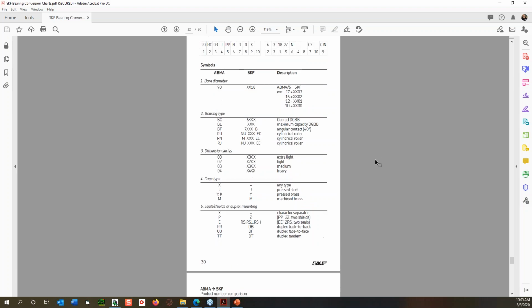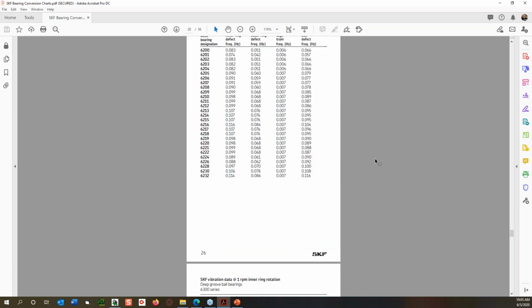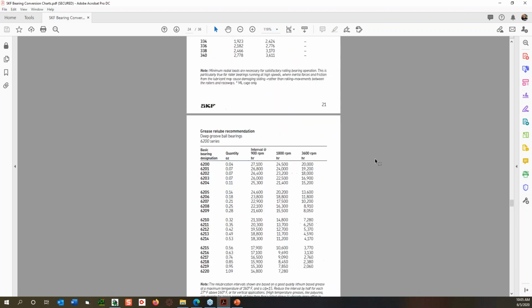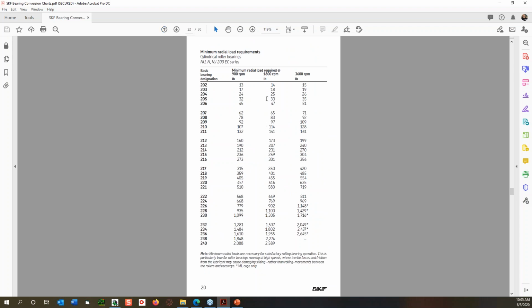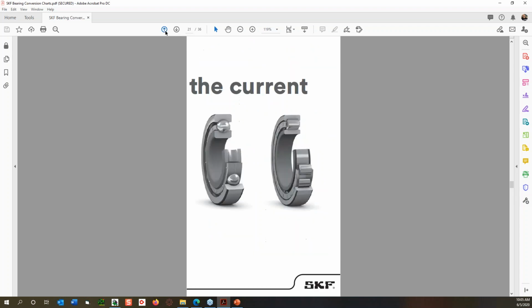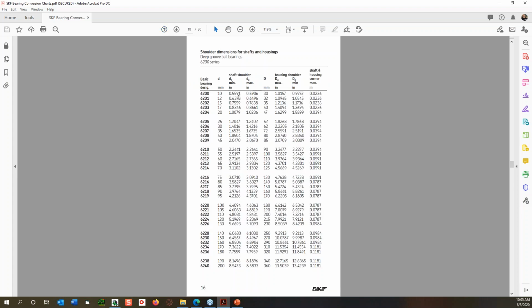So the 110, now we want to go back to the 200 series, 6200 series bearings and look for the bores. Let's go back. Okay, so I think, is this it? No, that's loading. Okay, dimensions, here we go. So I'm going to look for the bore, which was 110. So it's a 6222, which I had written down incorrectly last night because it was late. So it's a 6222 bearing. I'll note that on both of them. I'm going to randomly say the pump bearing sizes because I didn't write them down. So it's a 6222 bearing. Okay. Come down here, 110, 6222.